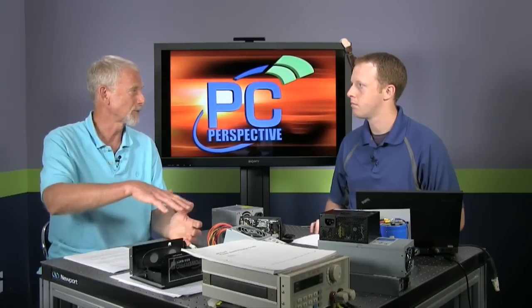So it'd actually have a longer life than one with a fan in that case. What wattages do fanless power supplies go up to in your experience? Typically 500 watts is the peak, 600 is the highest I've seen. The biggest contributing factor is that as efficiency keeps going up, heat dissipation goes down, so you can put more wattage through and dissipate the same level of heat.